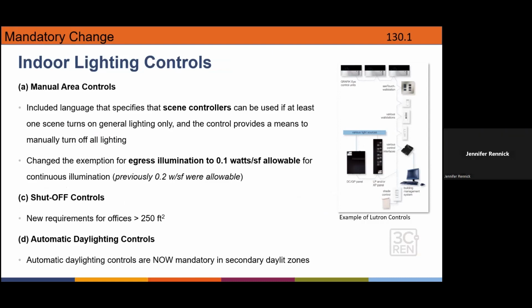Okay, so probably the biggest change on the indoor lighting controls is there's clarifying language that you can use scene controllers now, as long as the scene controller is able to do what it's supposed to do to meet the energy code. And automatic daylight controls are now mandatory for the secondary daylight zone. So basically, some things that were prescriptive are now mandatory.